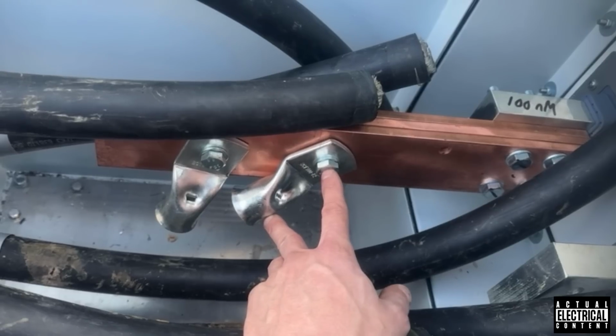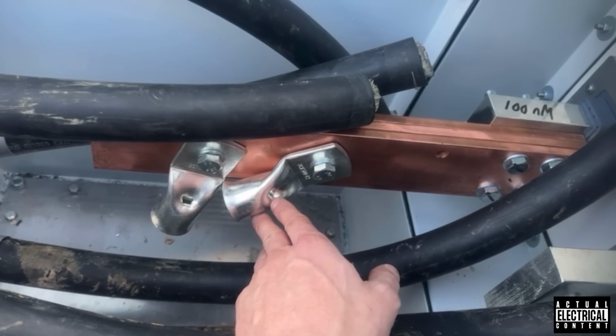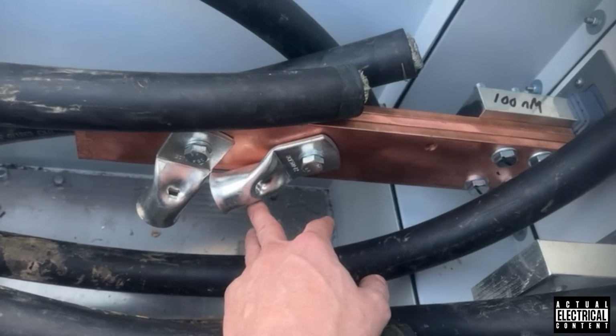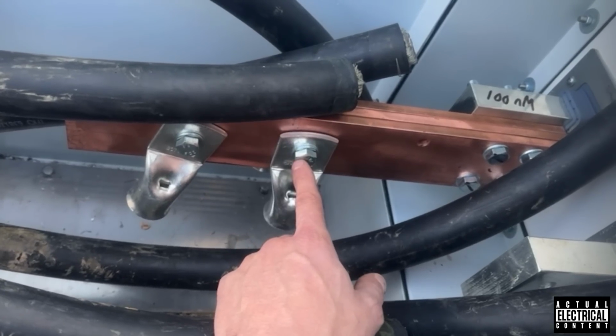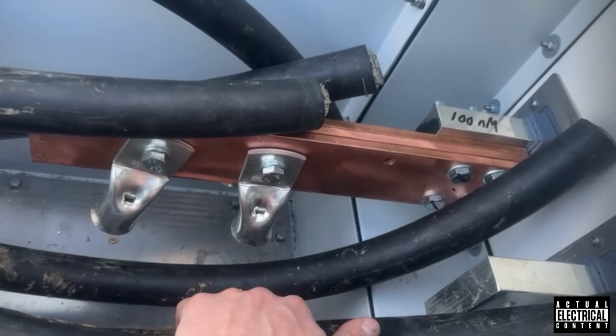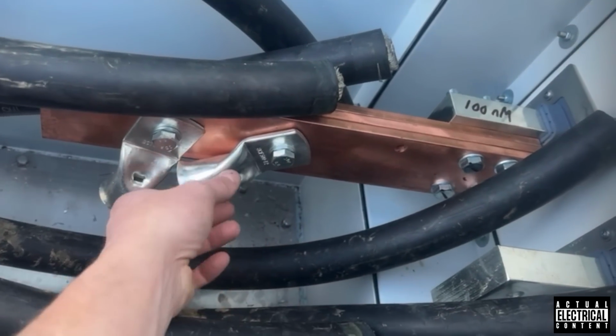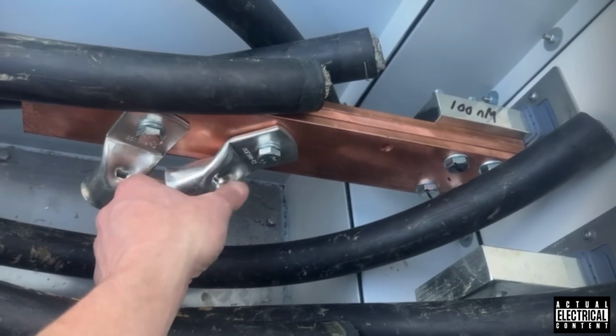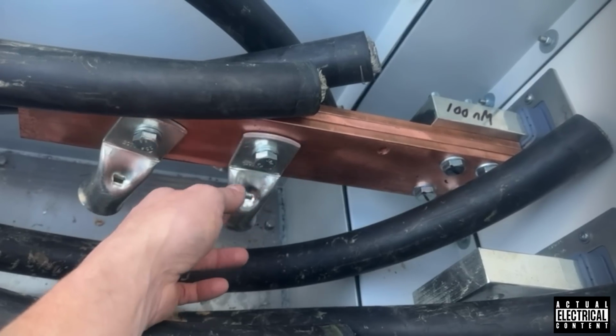So we need to get the measurement right. Once we cut this cable to go in this lug, we're absolutely committed to going in the hole, because there's no slack, no jiggling around, no loops. That's got to be cut. If it's cut 5mm short, that hole will be 5mm short and we're in big trouble.